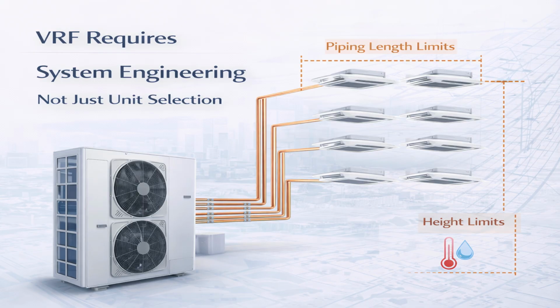VRF systems are often perceived as flexible and forgiving, especially because of their ability to modulate capacity and serve multiple zones. This perception sometimes leads to the assumption that VRF systems can adjust themselves even if selection or layout is not perfect. In reality, the opposite is true. VRF systems require very careful system-level engineering. Performance is not determined by a single unit, but by how the entire system is configured.